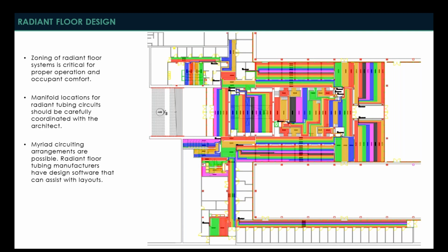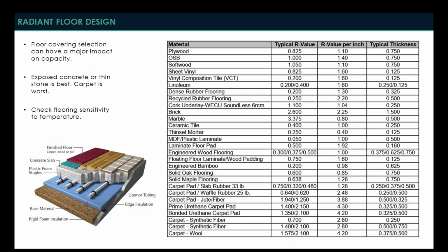You can give them your loads, surface temperatures that you're looking for, building constructions, and they can work with you to help develop these circuiting layouts. And finally, one thing that's very important to talk about when we talk about radiant floor design is floor coverings. In an ideal scenario, we're not providing any floor coverings at all because anything that we put on top of this radiant slab is going to be an insulator and it's going to reduce the capacity of that slab.